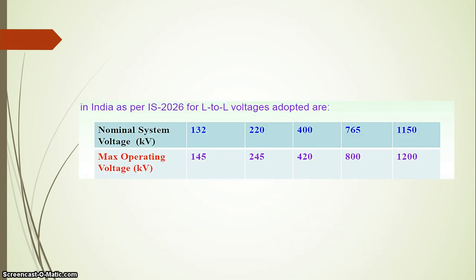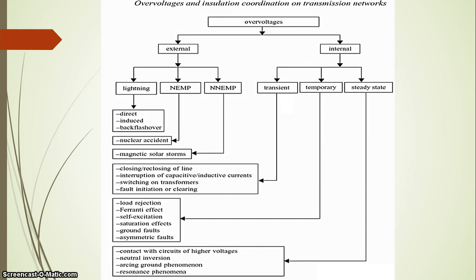In India, as per IS standard 2026, for line-to-line voltage: if the nominal system voltage is 132 kV, the maximum operating voltage is 145 kV. For a 400 kV nominal system voltage, the maximum operating voltage is 420 kV. The 220 kV transmission lines and substations are most common, having a maximum operating voltage of 245 kV.